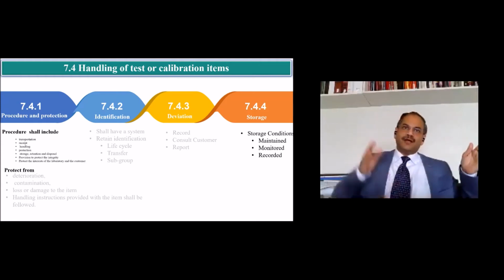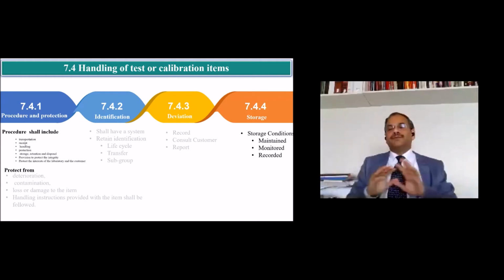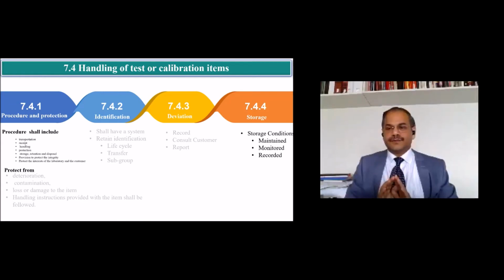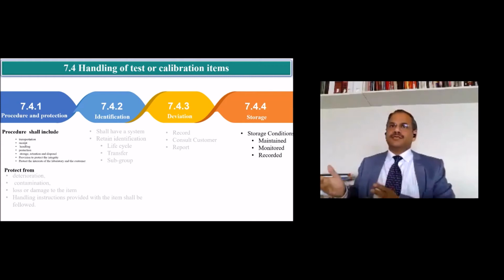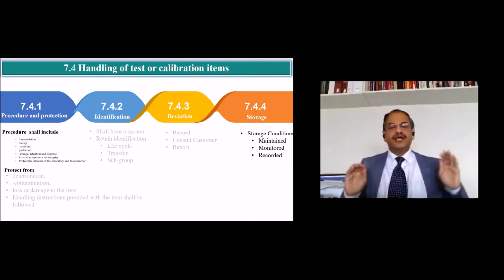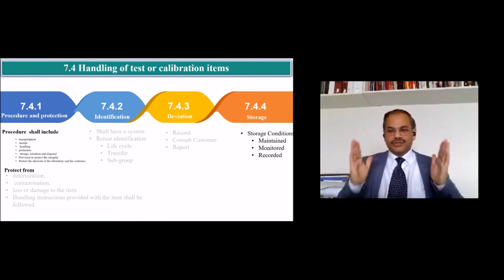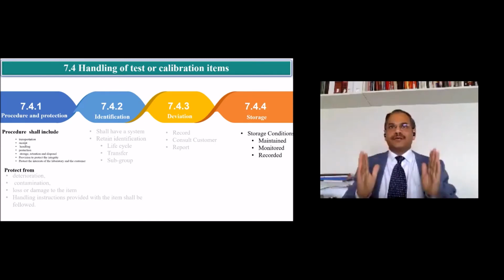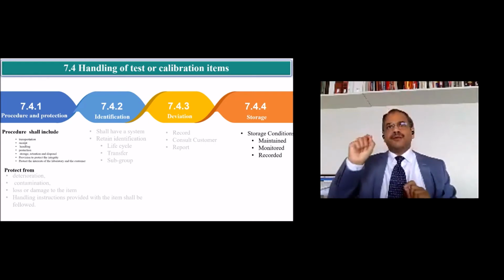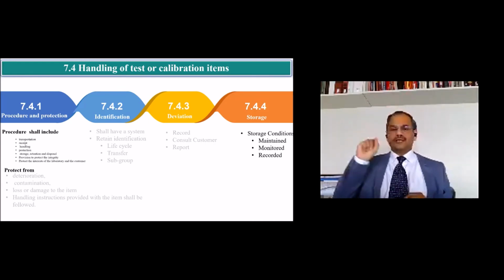At the end of the day, are you going to dispose of the sample or retain it? It depends on your customer's requirement and your agreement with your customer. You may dispose of it, or retain it for 1 month, 3 months, 6 months, whatever your agreement is. But you shall have a clear, documented procedure and record for all your samples, the test items and calibration items received in your lab, from cradle to grave. In some cases, if there is a specific requirement of temperature or humidity for retaining those samples, you have to maintain and monitor that and ensure it is being taken care of properly. So these are all the requirements on sample handling.